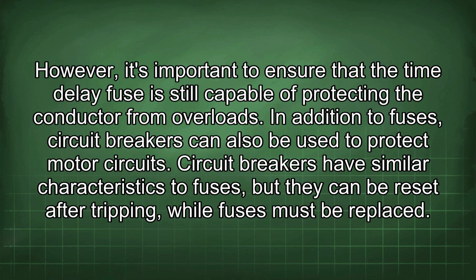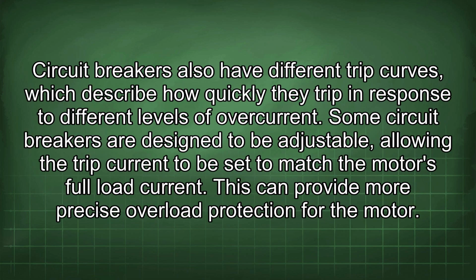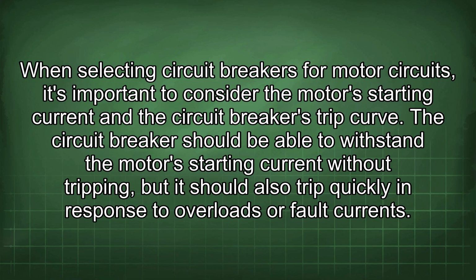In addition to fuses, circuit breakers can also be used to protect motor circuits. Circuit breakers have similar characteristics to fuses, but they can be reset after tripping, while fuses must be replaced. Circuit breakers also have different trip curves, which describe how quickly they trip in response to different levels of overcurrent. Some circuit breakers are designed to be adjustable, allowing the trip current to be set to match the motor's full load current. This can provide more precise overload protection for the motor. When selecting circuit breakers for motor circuits, it's important to consider the motor's starting current and the circuit breaker's trip curve. The circuit breaker should be able to withstand the motor's starting current without tripping, but it should also trip quickly in response to overloads or fault currents.